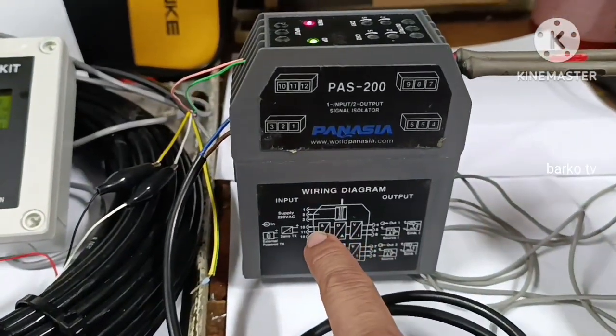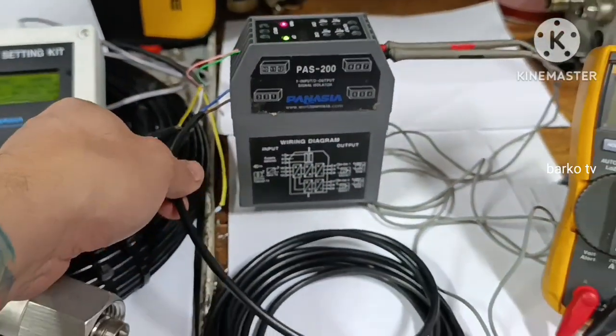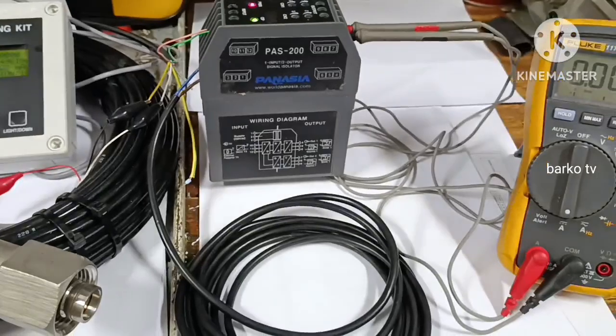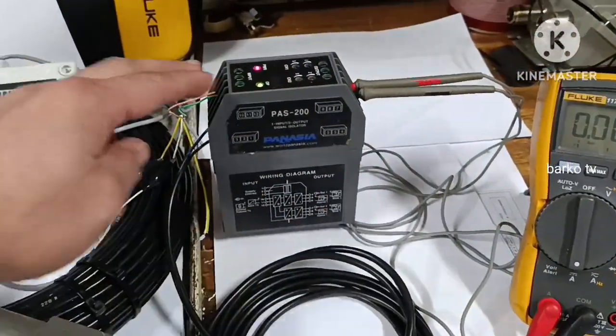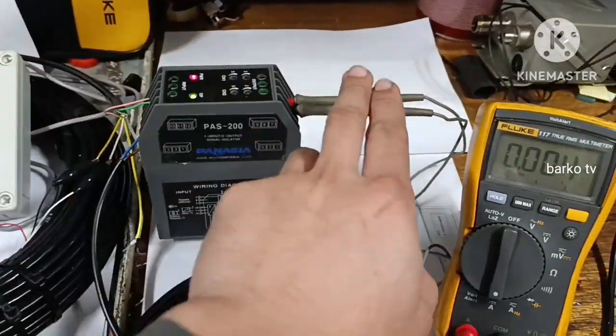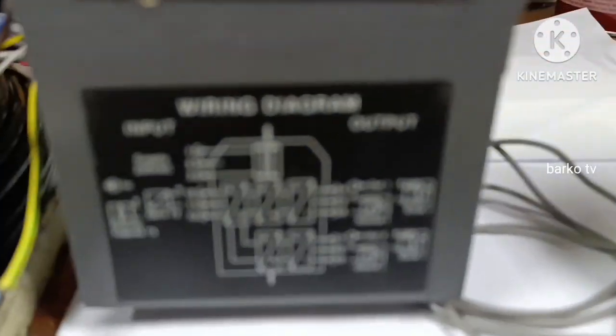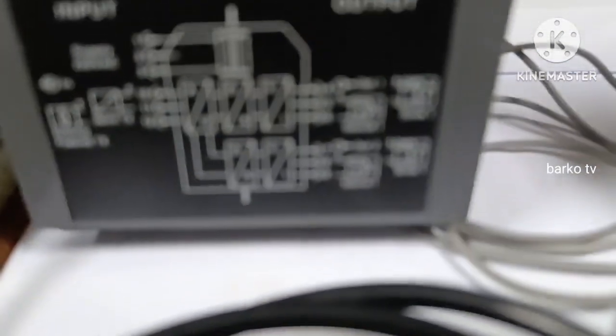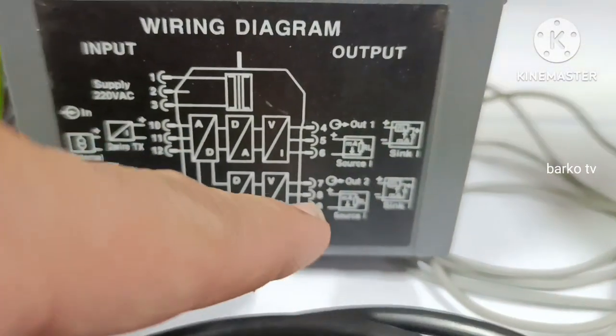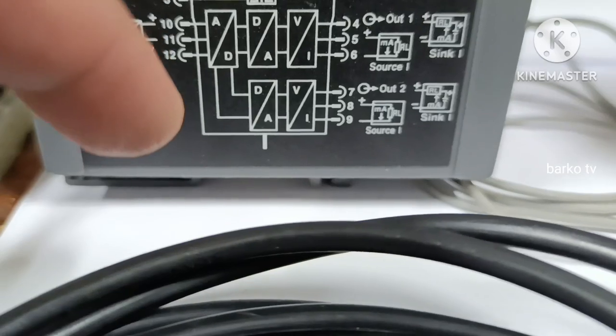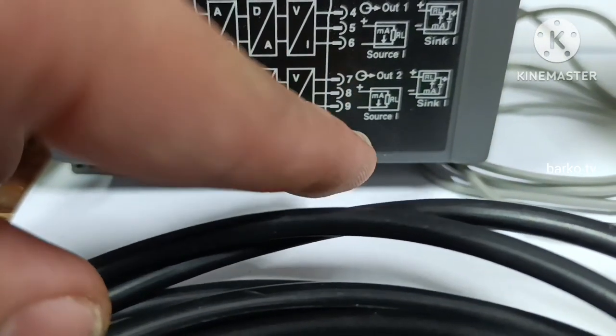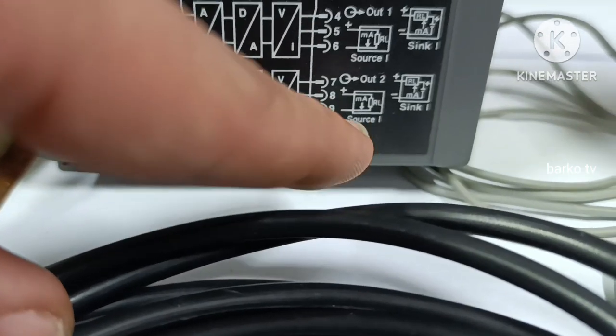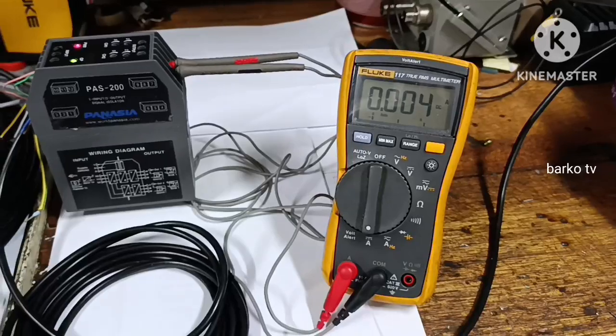The two wires pink and green going to this module, input 4 to 20 and output. There are two outputs also 4 to 20, channel 1 and channel 2. One input and then two outputs. Channel 1 is going to the alarm system and channel 2 is digital indicator or vice versa.